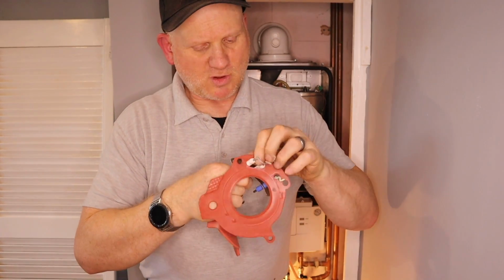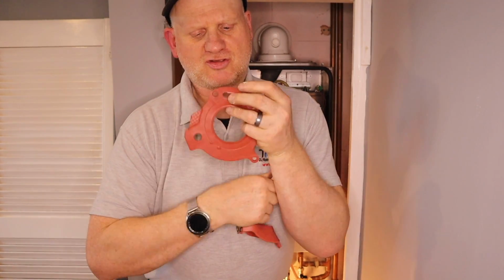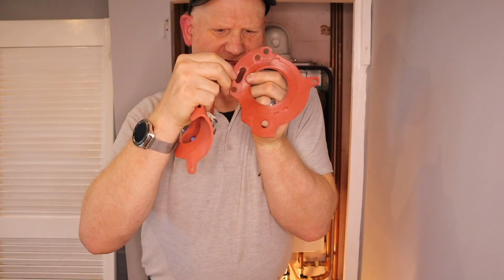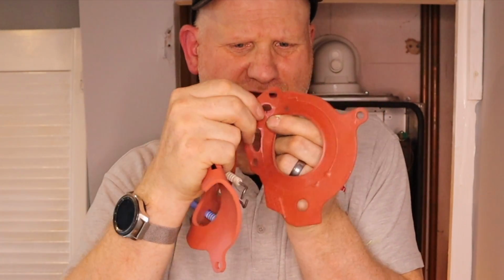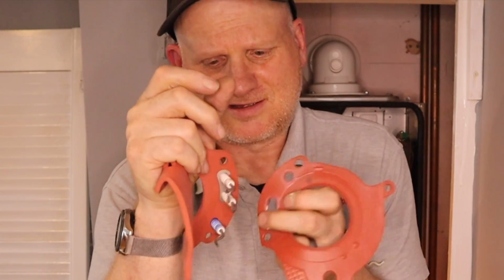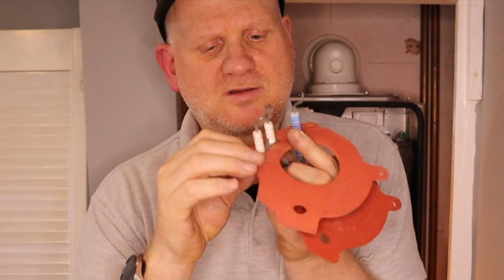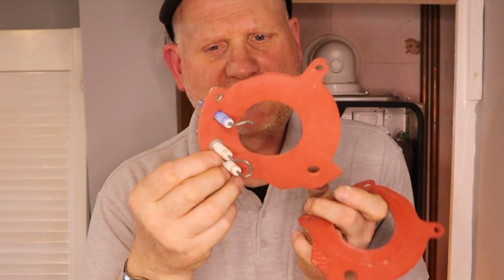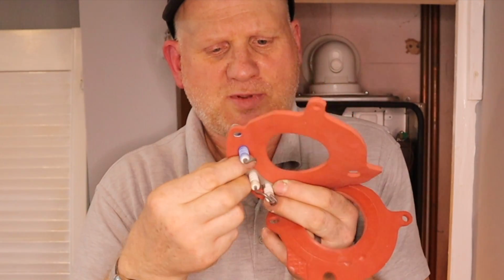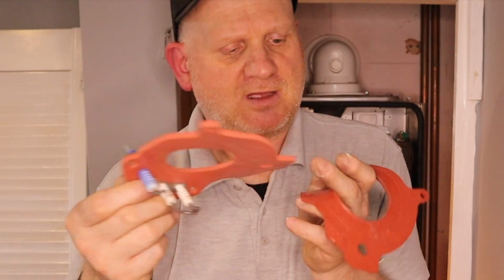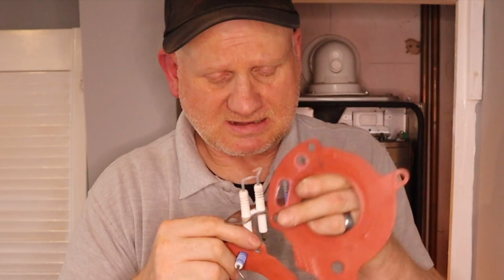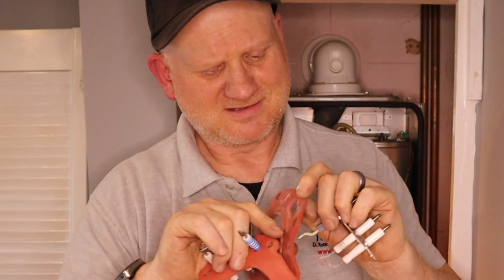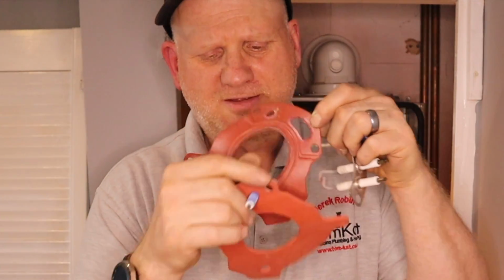And you can see now why it is important to change these, because I don't know if you can see that. It's all broken, cracked up. It's no good. So they now put this clamp on the bottom there to stop any heat getting through. So one of the reasons why we need to change these all the time. And you can tell from the way this gasket is that it's probably the original one.